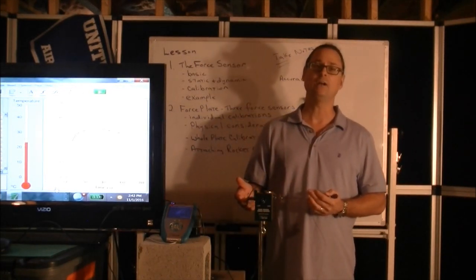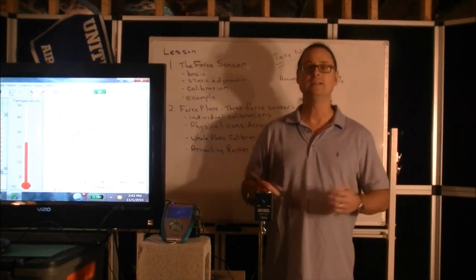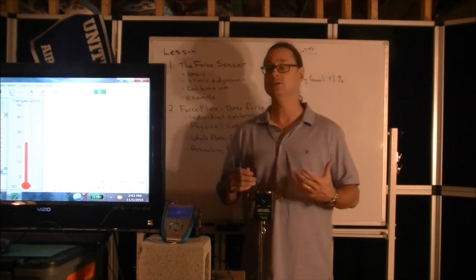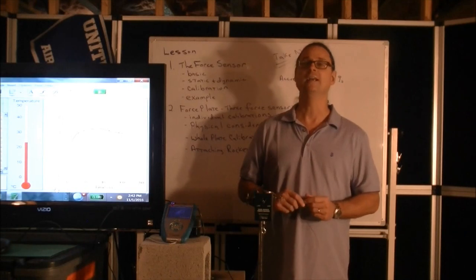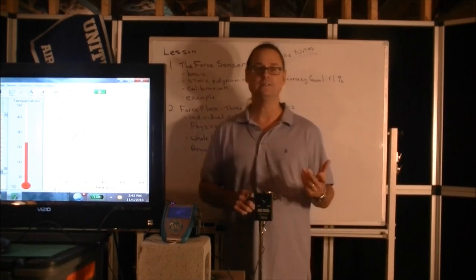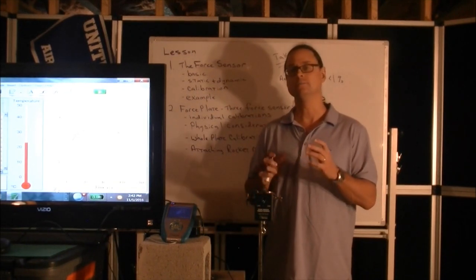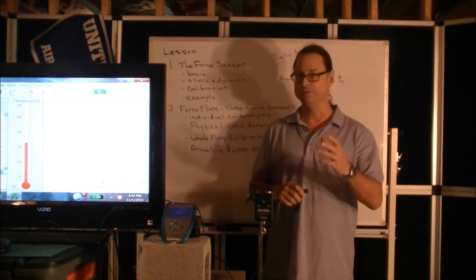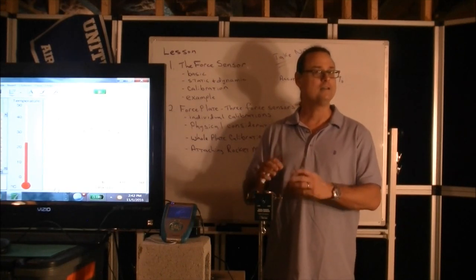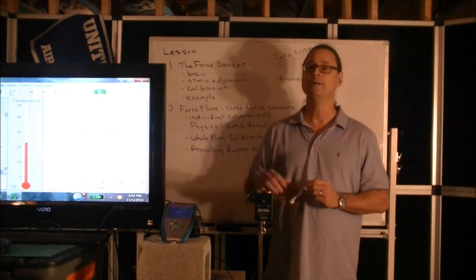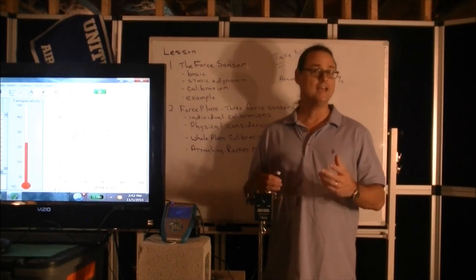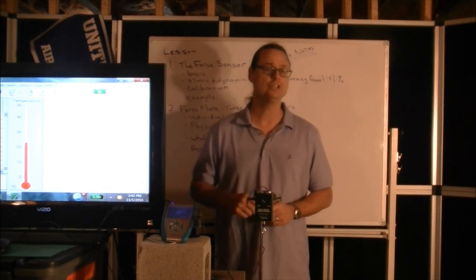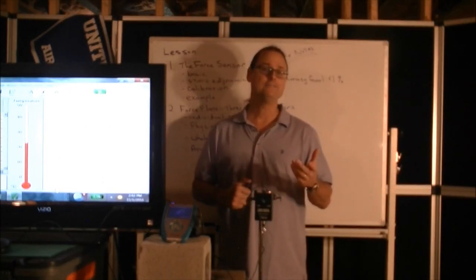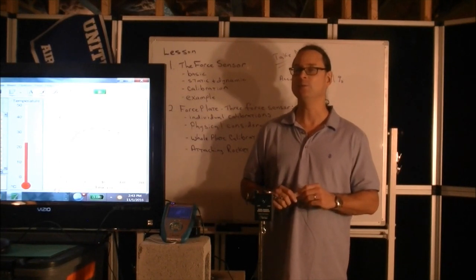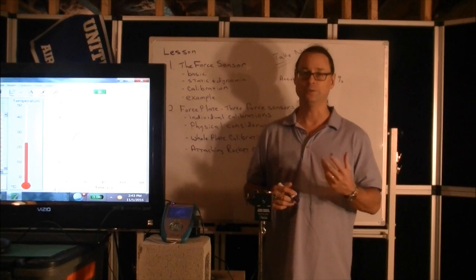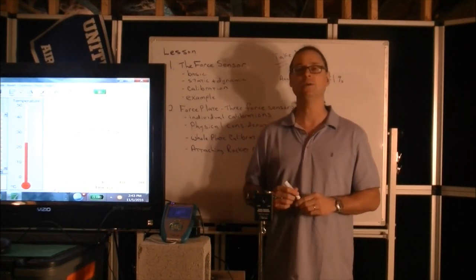Well, if we wanted to test the accuracy of the temperature probe, since we're close to sea level here, what we'd probably do is get some distilled water and boil it, and measure the temperature of boiling distilled water, and that is defined to be in the metric system 100 degrees Celsius. Then you could take an ice water mix. Again, you'd use distilled water to really do this accurately. Freeze some distilled water into ice cubes, crush the ice cubes, get about a 50-50 mix of the crushed ice cubes and distilled water, put the temperature probe in the ice water bath, and then if you're really accurate, your temperature reading should be 0.0 degrees Celsius. And if your temperature reading of your ice water mix isn't exactly 0.0, or in your boiling water isn't exactly 100.0, then you have a sense for how inaccurate your thermometer might be.